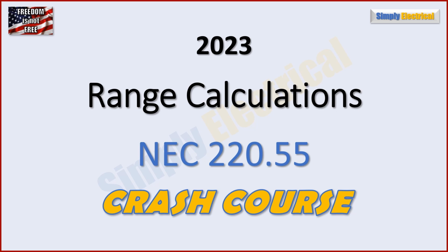Now this is on the 2023 code, but it also is for any code cycle before that as well, any of them that are in use today across the nation, because they haven't changed Article 220.55 really at all. There are a few changes, but those are just in the notes to the table, and it only affects branch circuits, not load calcs.